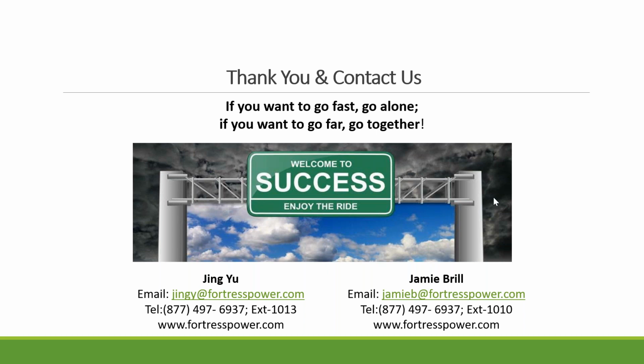Chris asked: I'd like to see an example of sizing your LFP versus FLA—I say FLA because that's what most of us old-time installers have been using. A commonly sized off-grid system is 1350 amp hours, or 64.8 kilowatt hours at 48 volts. So how many eVault 18.5 kilowatt units would I need to replace my clients' old FLA?